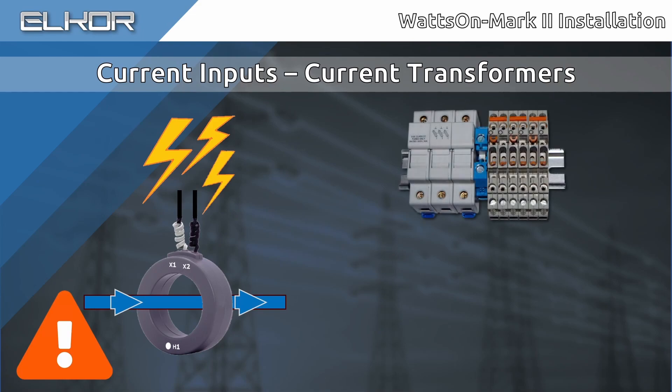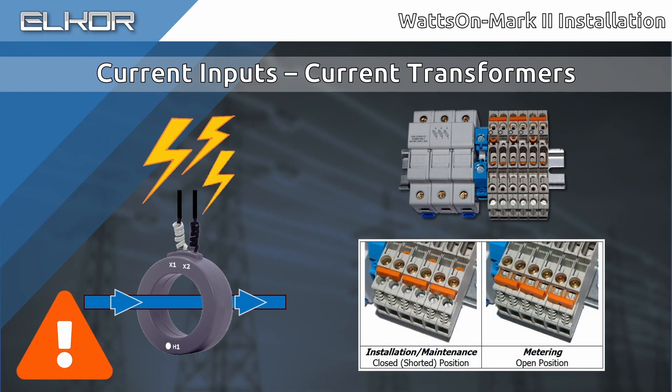If a shorting block like the Elkor iBlock is used, ensure that the shorting bars are in the shorted or maintenance position. While millivolt, milliamp, and Rogowski coil CTs do not produce dangerous output voltages like 5-amp CTs, it is still not recommended to work with the CTs energized.